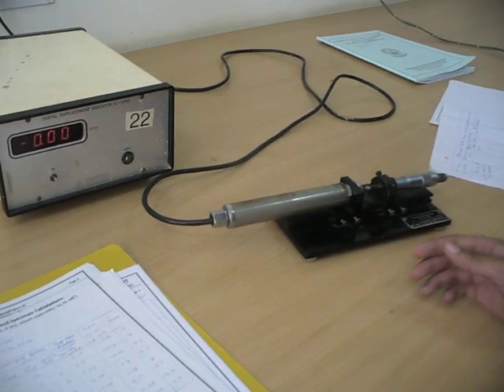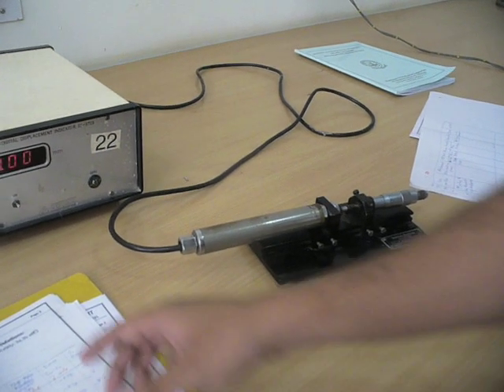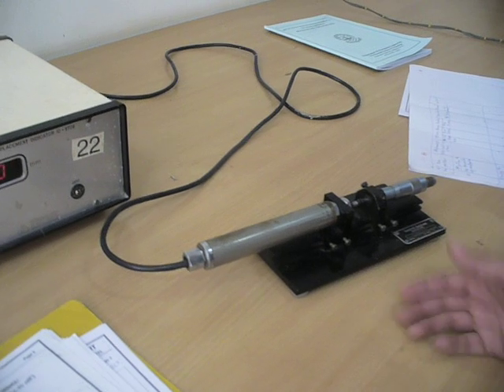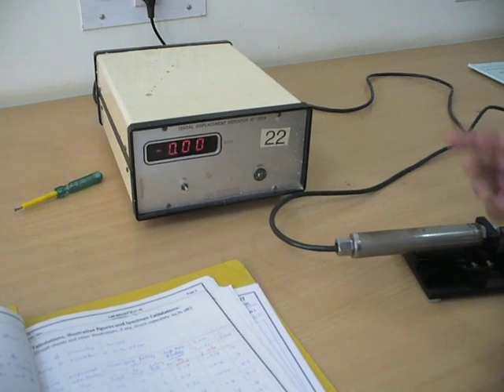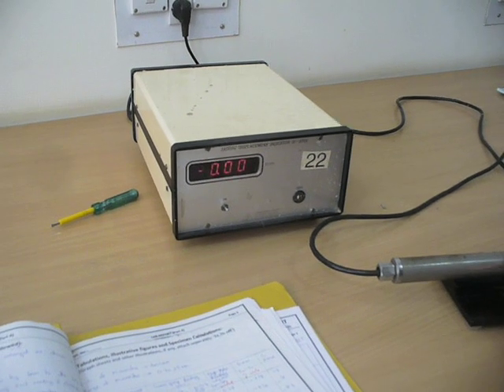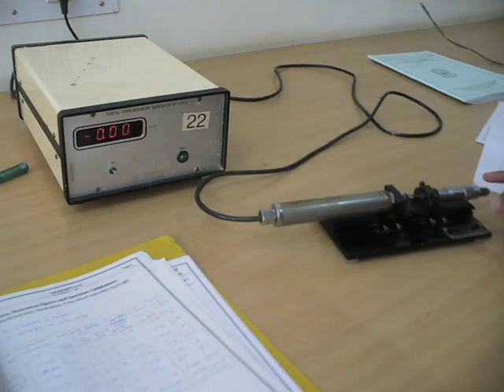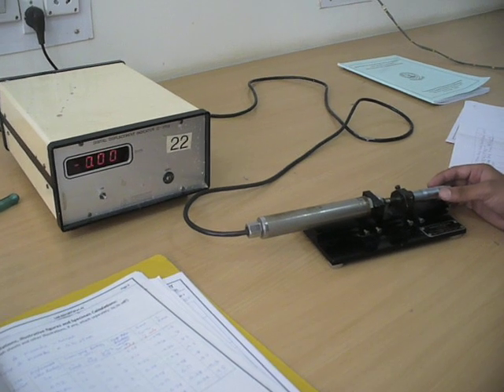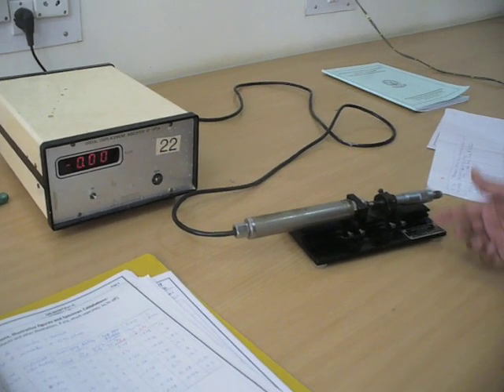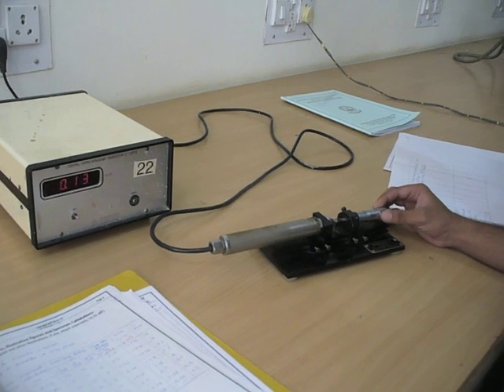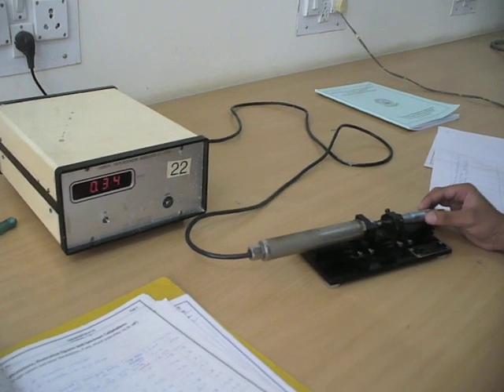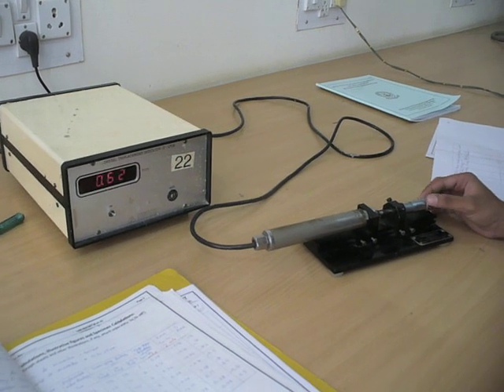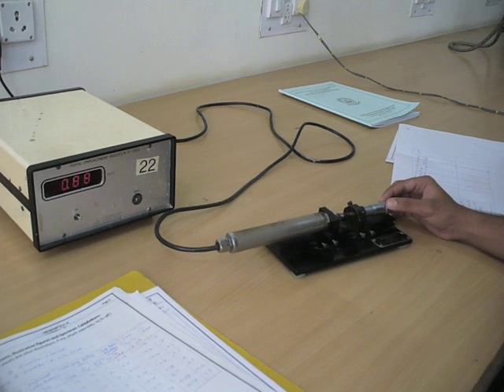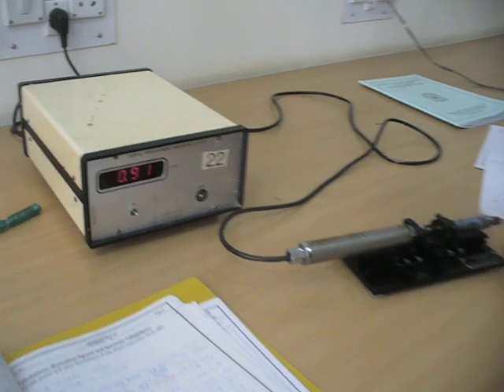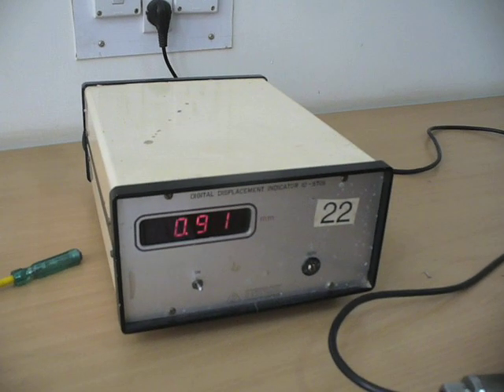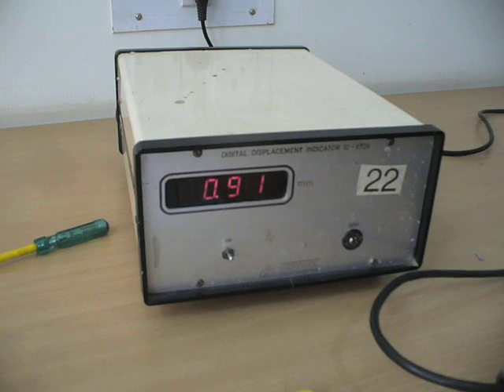First we move the spindle of the micrometer by 1 mm and check correspondingly how much the display meter indicates, meaning how much the LVDT records. The least count of this is 0.01 and the pitch is 0.5. So we need 2 revolutions of the spindle to move by 1 mm. Right now we're going right side of null. The micrometer has now moved by 1 mm, and our display meter is showing a displacement of 0.91 mm.